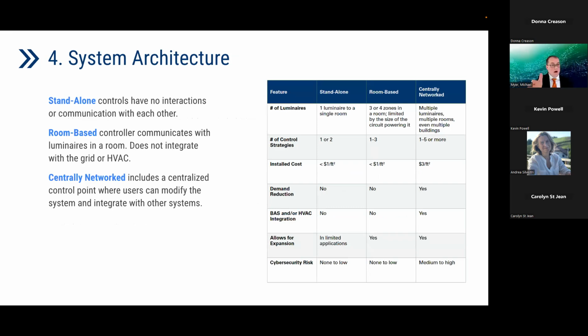So these 3 columns show you your different options. If you have a small space, standalone makes sense most of the time, but not all the time. So you might think about that. It gives you an idea. As you start layering in the number of control strategies you might have, again, that might tell you whether or not you want to have a standalone system versus a centrally networked system or a room-based system. If you're going to start doing demand response, again, that's going to tell you what some of your requirements are. Or if you're concerned about integration, those types of things.